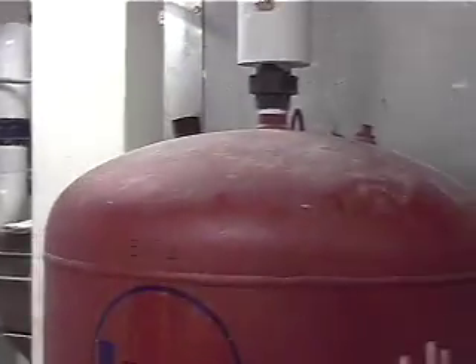All right, now we'll be talking about the expansion tanks for the system. This is a bladder type expansion tank. Really, there's no maintenance. All you want to do is make sure that bladder holds the pressure it's designed for. In the O&Ms, I did bring one here. I'd like to say too, there's a gauge on it.